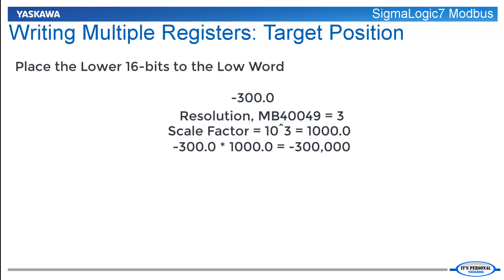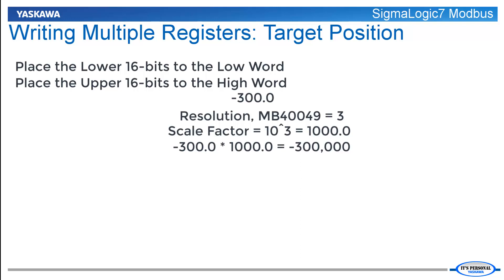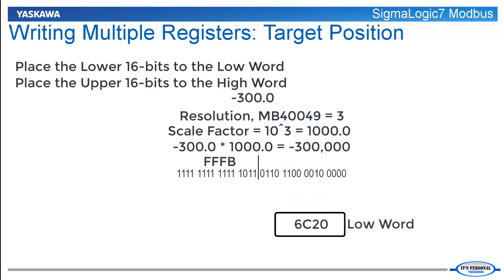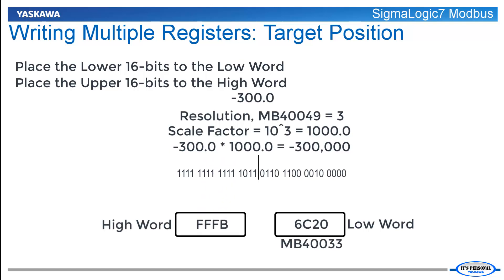Next, place the lower 16 bits into the low word and the upper 16 bits into the high word. It is easier to understand where the bits and bytes are located by expressing this number in binary and hex. The hex equivalent of negative 300,000 is FFFB6C20. So 6C20 will be placed into the low word at register 40033, and FFFB will be placed in the high word at register 40034.